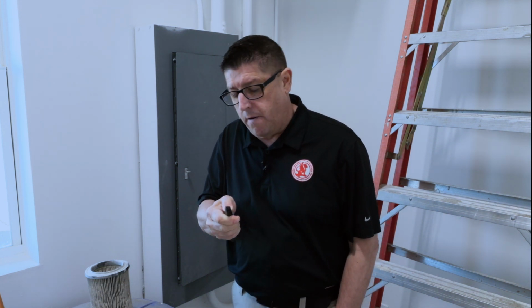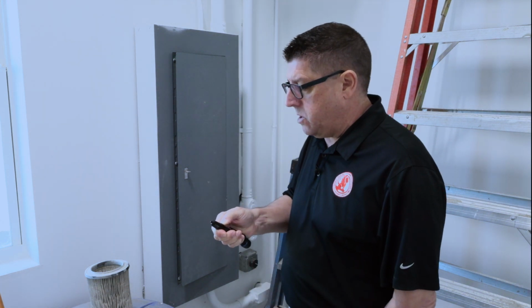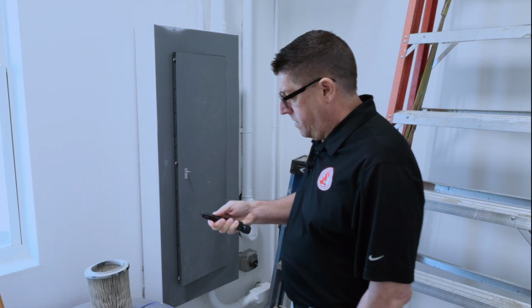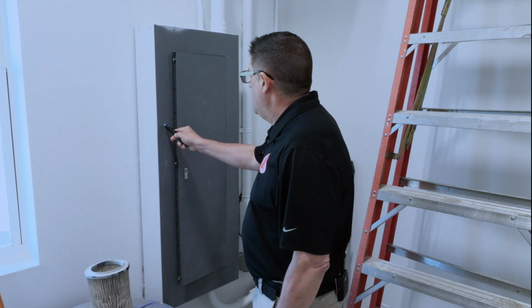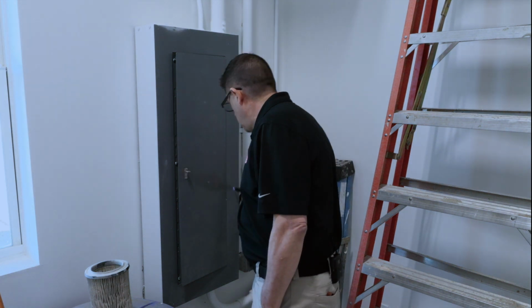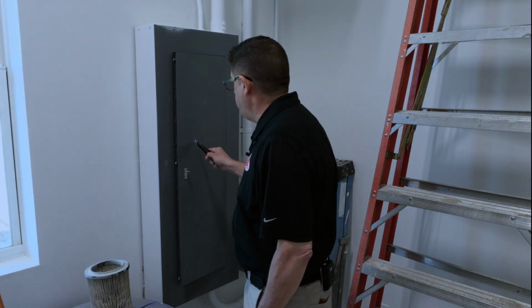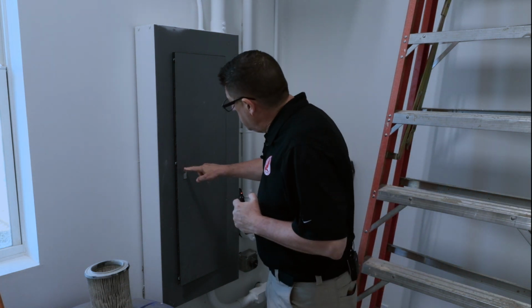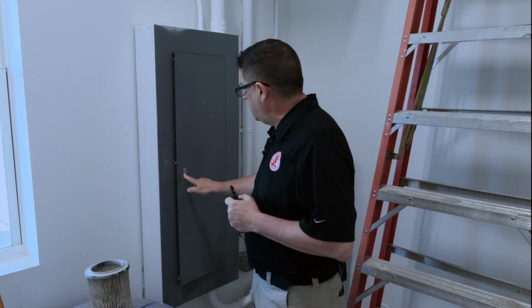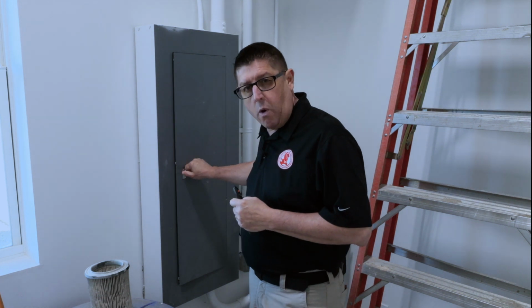Now, before I touch the panel, once again, I am going to use my non-contact voltage detector, and I am going to touch and make sure that I have no loose voltage around this panel. What's interesting on this inspection is you can see that there's a key here. This is a Square D panel. This is a Square D key.